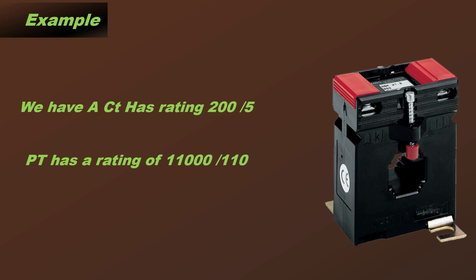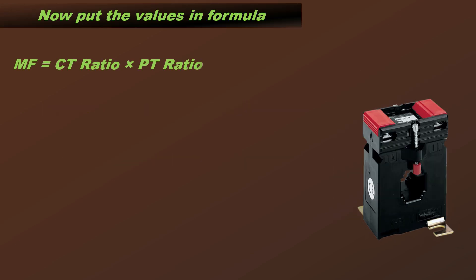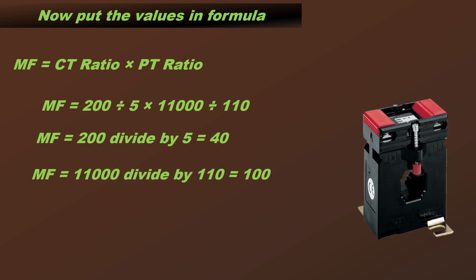Now putting the values in the formula: Multiplication factor = (200/5) × (11,000/110). 11,000/110 = 100. Multiplication factor = 40 × 100, so the answer is 4,000.